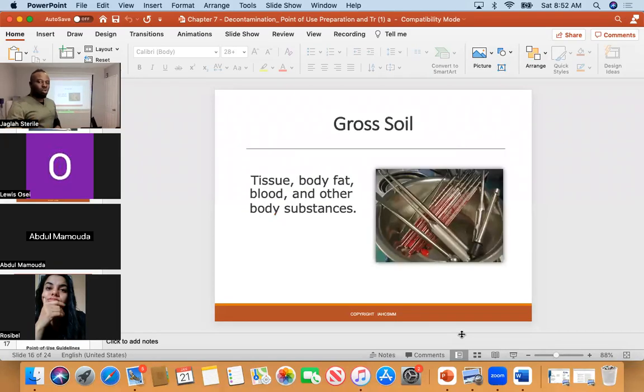Keep instruments moist. So after the instrumentation is wiped down, they still have to be sprayed with enzymatic gel. In the past, they would use a towel, a wet towel, and spread it on the instrumentation to prevent it from drying. Some would also leave it in a basin filled with water, and that creates a spill hazard. These are old techniques. I wouldn't say no longer used, some people may be doing it, it depends. But what we have now is a spray gel. After you arrange your instrumentation, you spray it and keep it moist, all right?